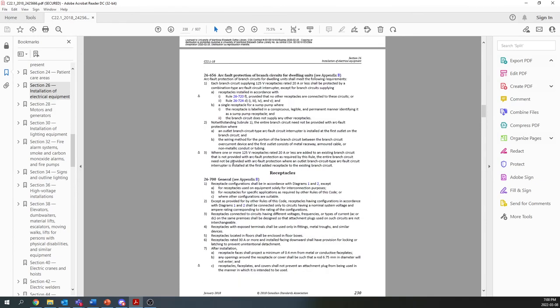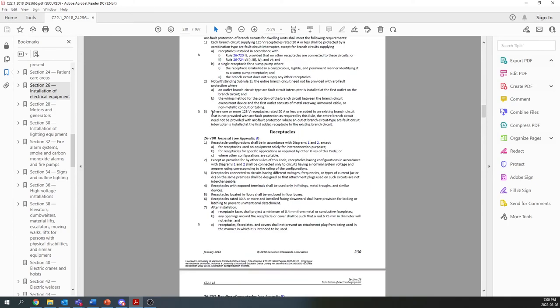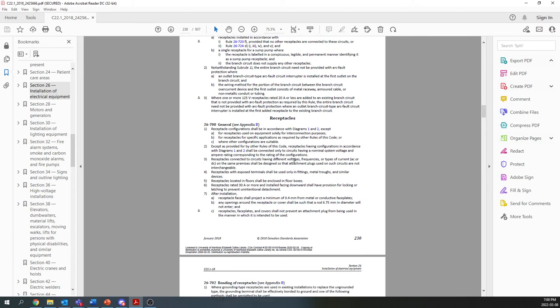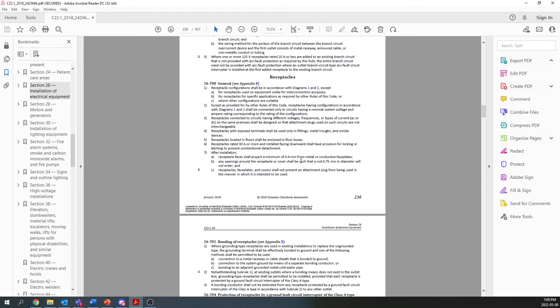There's also a bunch of stuff here on how many receptacles you can have on a branch circuit, and what installation configuration they should be in. So when you're doing a big commercial job or something like that, a consultant is doing that, they're going to have one or multiple detail sheets that say this receptacle should be installed in this certain way, and that would have to match what's in section 26 here.